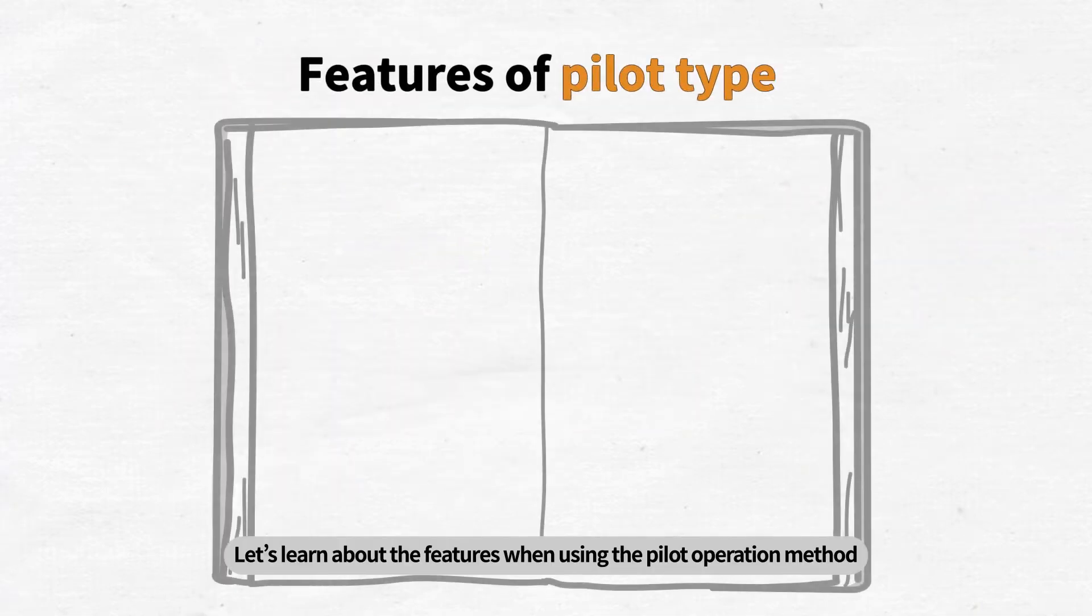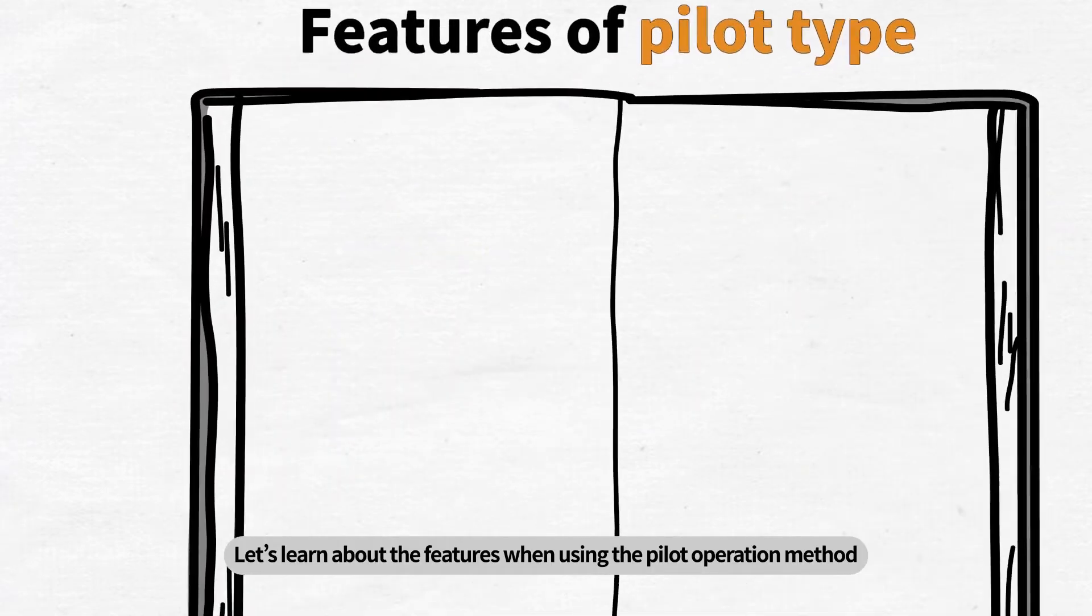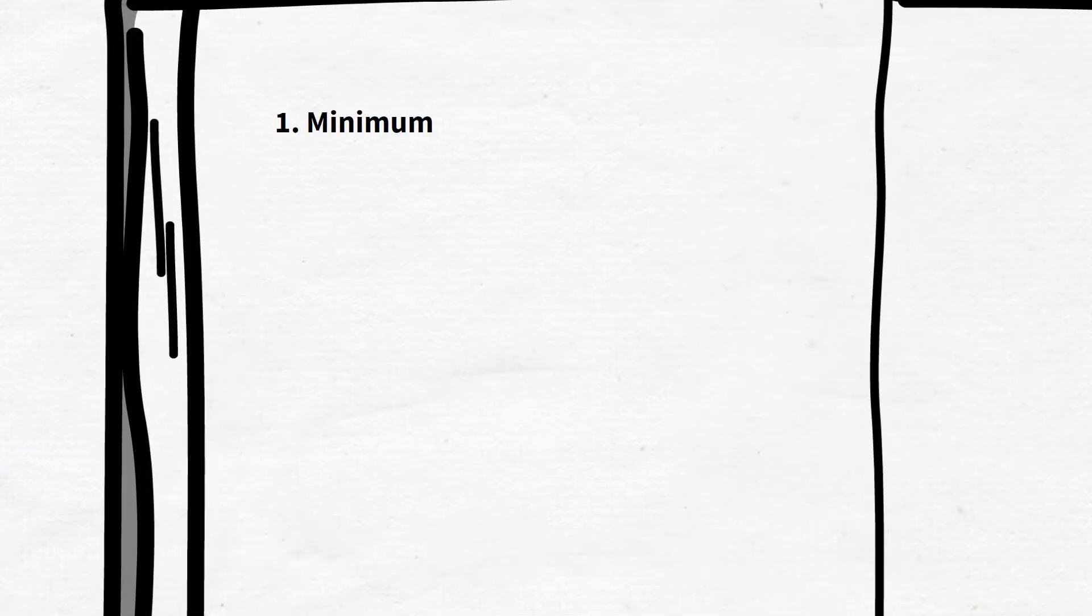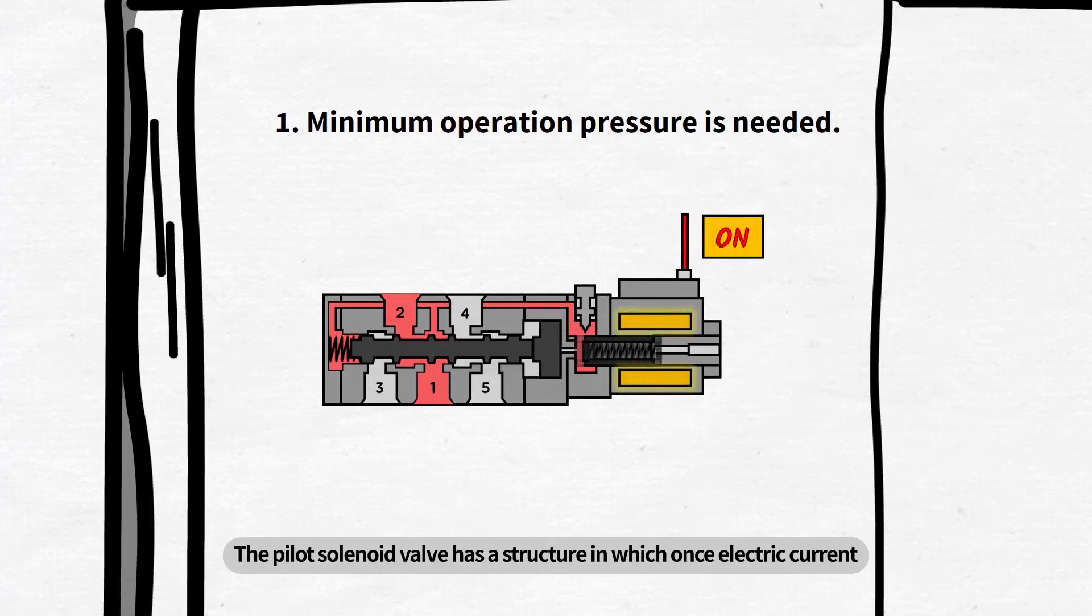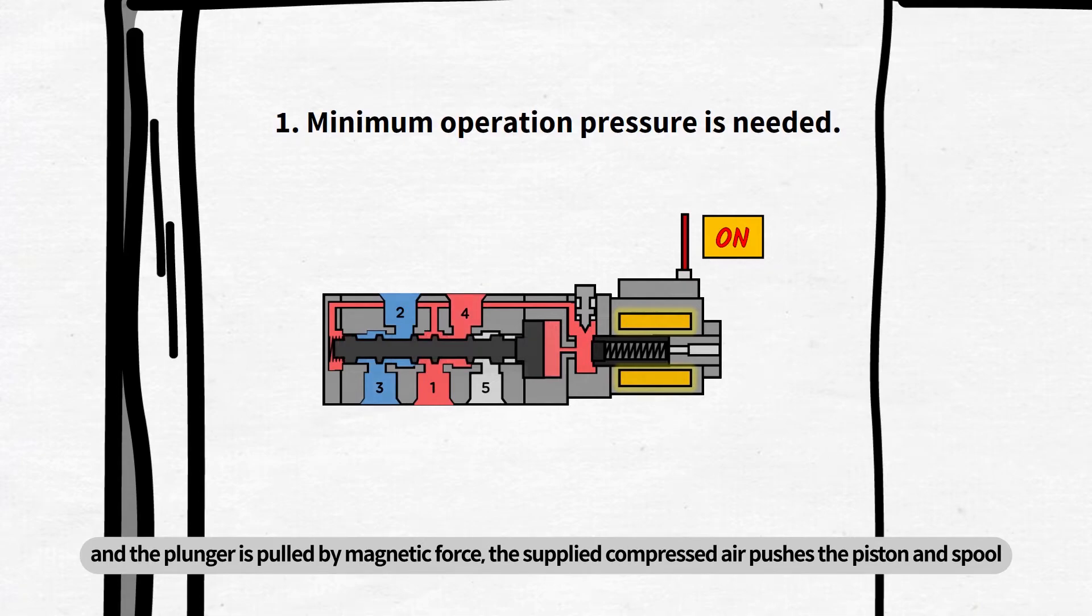Let's learn about the features when using the pilot operation method. First, minimum operation pressure is needed. The pilot solenoid valve has a structure in which once electric current and the plunger is pulled by magnetic force, the supplied compressed air pushes the piston and spool.